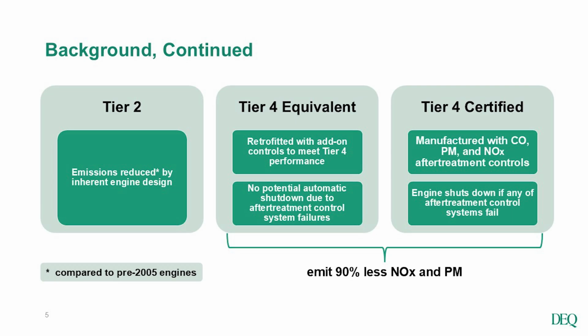In a Tier 4 equivalent genset, there is no potential automatic shutdown due to after-treatment control system failures, whereas with a Tier 4 certified genset, the engine shuts down if any of the after-treatment control systems fail. The key here is that both of these options emit 90% less nitrogen oxides as well as particulate matter, and that's the purpose of Tier 4 emission standards. I also wanted to stress that in DEQ issued permits, permit writers specify that gensets cannot operate unless after-treatment control systems are also operating.